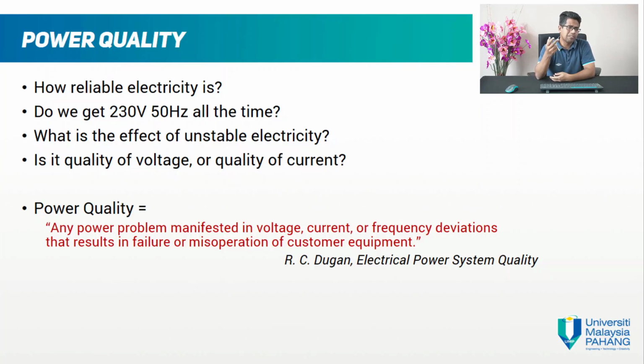So what are the effects of unstable electricity? There are a lot of effects when we have a lot of sensitive load, depending on how we tackle the problem. If we install good quality relays up to the standard, then we should not have any problem whenever a typical power quality problem happens. Let's say the voltage goes down to 0.8 pu, but only for 50 milliseconds. That shouldn't be any problem if the relay is good enough, if our setting is good enough.